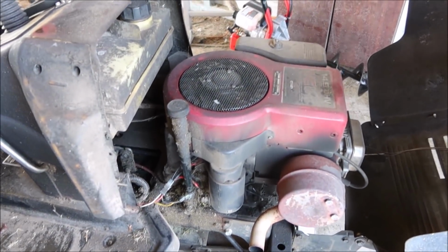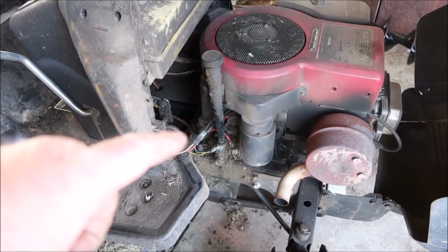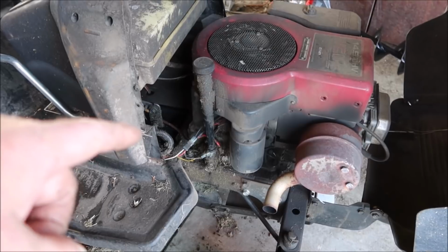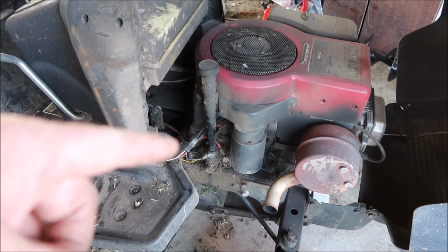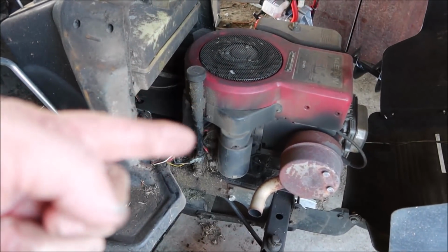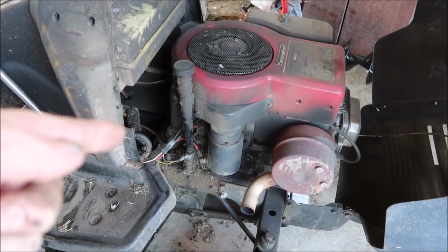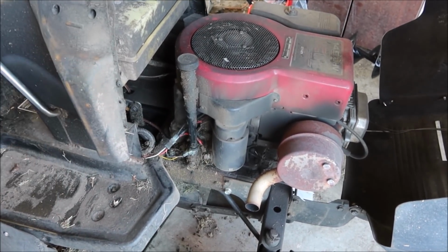So what we're going to do is verify that we have voltage to the plug, and then verify whether, downstream of the plug, we have a direct ground issue.